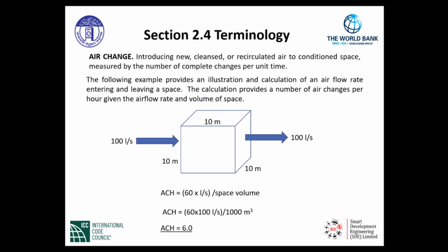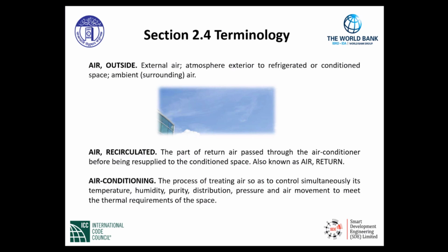The air change per hour expression, or the equation below, is as follows. The unit time we will use here is 1 hour. Air changes per hour equals the quantity 60 times the airflow rate in liters per second divided by the space volume. So in this example, we simply take 60 times 100 liters per second divided by 1,000 cubic meters. And the total air change per hour is 6 air changes per hour. Another definition, outside air. Outside air, by definition, is very specific here. It is external air, atmosphere exterior to refrigerated or conditioned space, ambient air, or we say surrounding air.